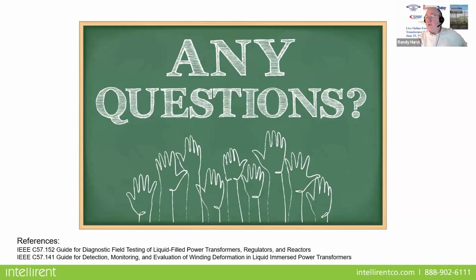Next question. How can power factor testing help a non-specialist understand whether a bushing is nearing failure? Are there simple signs or thresholds I should watch for? Yes, and that is again referring to your IEEE guides and standards. Just go to Google, type in IEEE standards for bushings, and all that information is there, including how much deviation represents a problem. What is my DGA telling me? What is my variable frequency power factor telling me? You've got to do a little bit of research. The standard is there in terms of whether I'm seeing something good or something bad.